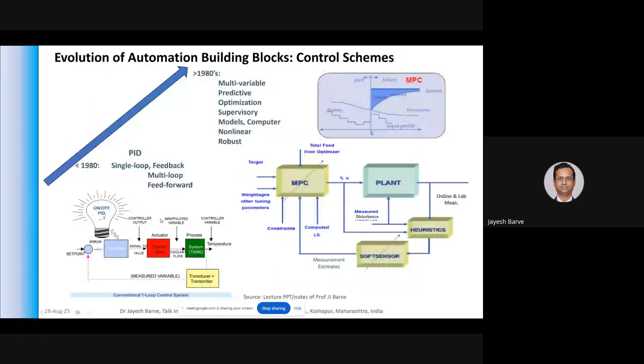Now, I talked about this high-end control algorithm—on the left side you see the automation building block for the continuous process we deployed, which is used in the cement plant. As I mentioned, we had a control room where field control data from the plant—from the cement mill, ball mill, vertical roller mill, and kiln—comes through PLCs and different sensors into the control room. From the control room, what we added in the hierarchy was a dynamic and steady-state optimization layer.